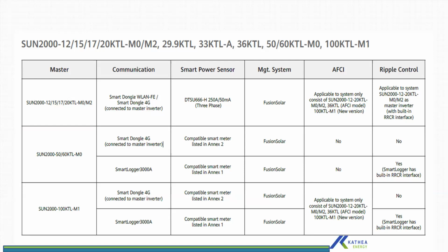It will come with built-in arc fault protection. And then for ripple control, for larger ranges you can use a smart logger. For the smaller ranges, the inverters already have ripple control built in, with four digital inputs. And then for connection, there are meters that are compatible with the system. We mainly distribute the Janitza, which is one of the range of meters that is compatible.